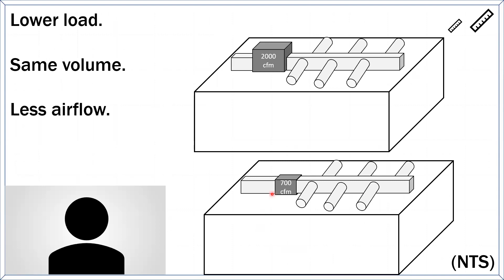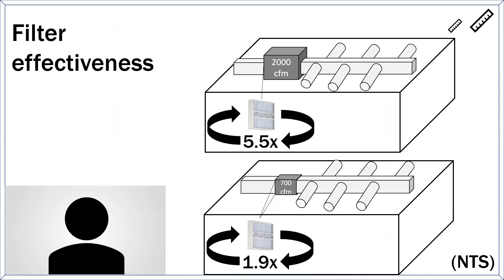Well, one of them is filter effectiveness. We don't really think about this, but we used to cycle the air through that filter, the whole volume of air in the house. If this was 2000 CFM, we'd cycle the air through the filter 5-6 times. New modern house with a much lower airflow, twice. That filter is not being as active at removing particles from the air, right? No wonder we say we want more outside air in here, right? Because the filter isn't cutting it, right? We do those air metering to indoor air quality meters, and we find that things aren't great. This is one of the reasons.